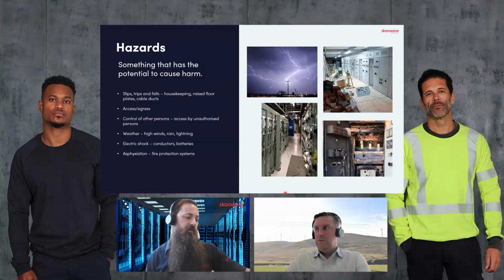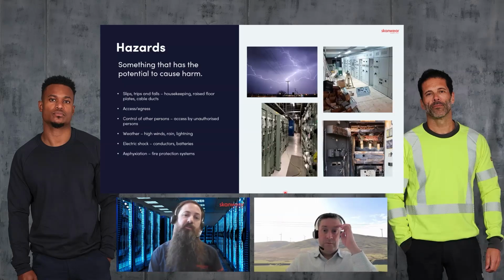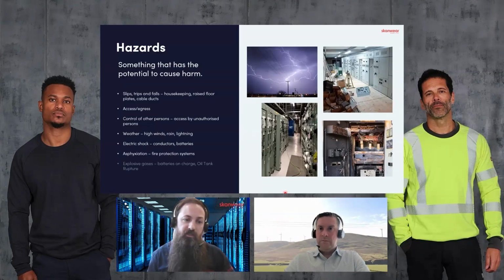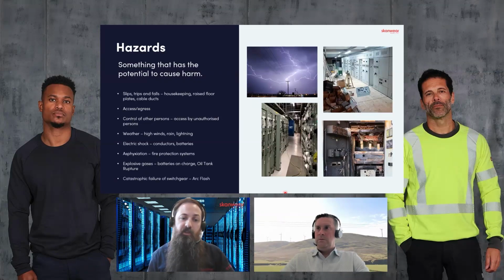Asphyxiation, maybe not as common anymore, but depending on what fire protection systems you have, there might be an asphyxiation risk, things like CO2. I'd like to think older ones like BCF and Halon aren't used anymore, but you do see CO2 quite a lot still on networks, which doesn't support life. So make sure that you've got a process for isolation of those systems. Explosive gases, potentially from batteries or in the event of a catastrophic failure of oil apparatus, oil-filled switchgear or oil-filled transformers. And obviously the catastrophic failure of switchgear, arc flash, which is a low frequency event, but obviously high consequence in the event that it happens.